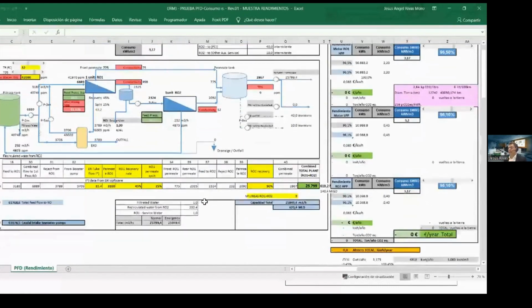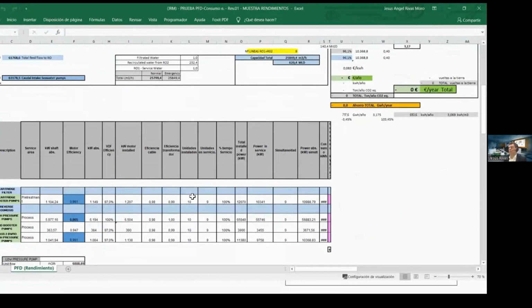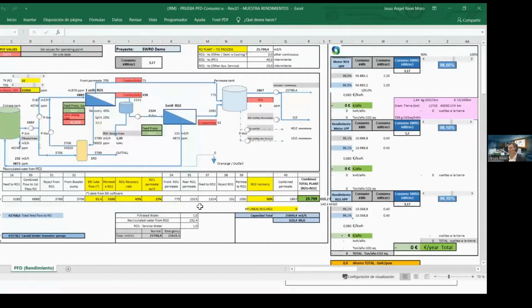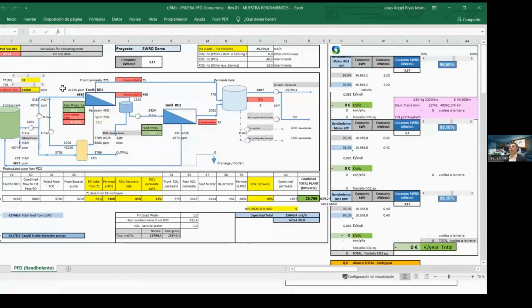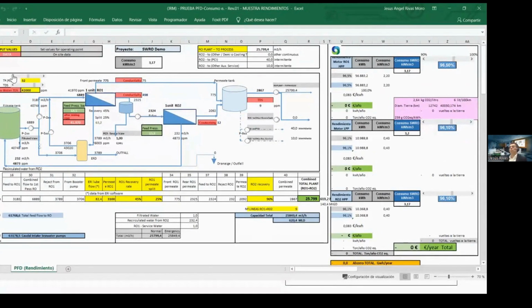I'm going to show you all these calculations and all the calculations behind this Excel. You can summarize that. I have this presentation with only modifying the motor efficiency for the cartridge booster pump, the low pressure pump, the high pressure pump, and the second pass RO pump. I'm not talking about the drives. We will show you this later, or the other efficiencies, transformer, the wire, all these calculations that your process and electrical people should prepare. At the end, it gives you a power consumption. Okay, sorry, because of the internet. Let's check a standard. Pay attention to one example. 3 point something. You have the power consumption here.